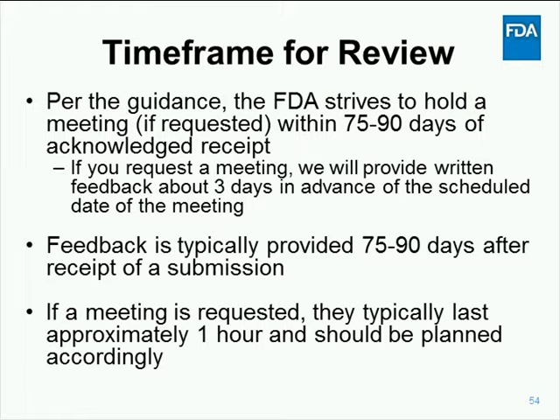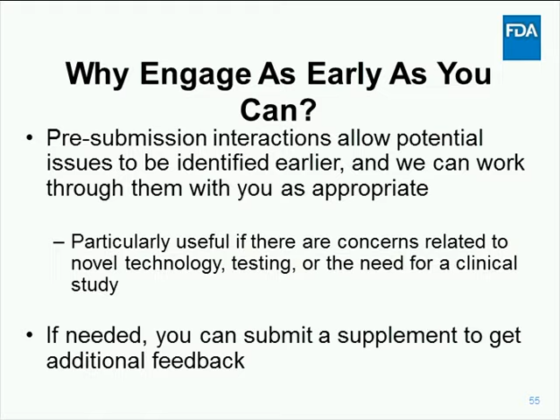And I'd like to point out that you can engage with us in a pre-submission while your device is still in early phases of development. We believe that early FDA engagement with a pre-submission represents a chance to identify potential issues and address them appropriately. This can be particularly helpful if you have very novel device technology or if you'll need substantial testing or clinical data to support your device's performance claims. After an initial pre-submission, you're always welcome to submit a supplement at a later stage in your device's development if you'd like feedback then.